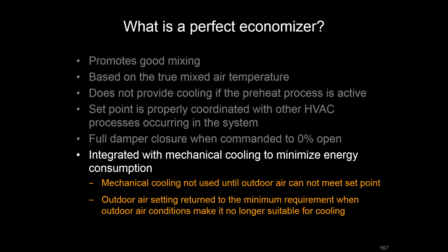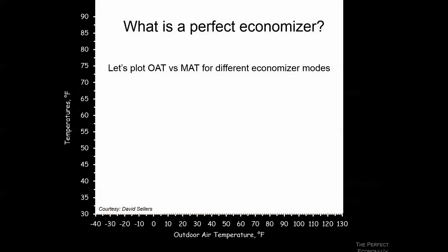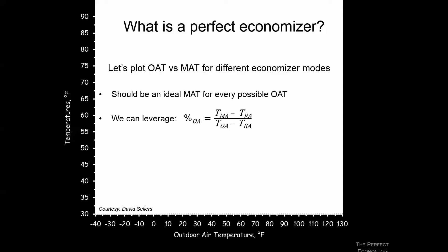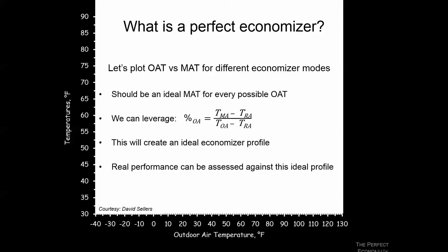With those modes and operation considerations in place, let's look at what mixed air temperatures we should get at an array of outside air temperatures. For every outside condition, our ideal economizer should reach a specific mixed air temperature. Using conservation of energy and mass and treating air as an ideal gas, we derive an equation based on the ratio of economizer temperatures to give us the percent outside air being brought in, creating an ideal economizer performance profile.